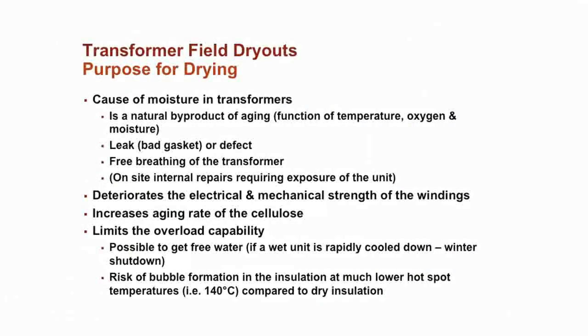Once you see that the moisture level inside the transformer is creeping up, a very good thing that can be done is to dry out that transformer. Again, this is something you might contemplate doing at midlife of a transformer. By drying out the transformer, you reduce the aging rate, and you can also reduce dielectric risk. If the moisture becomes so much that you compromise the cellulose-oil insulation structure of the transformer, that can increase the risk of failure.